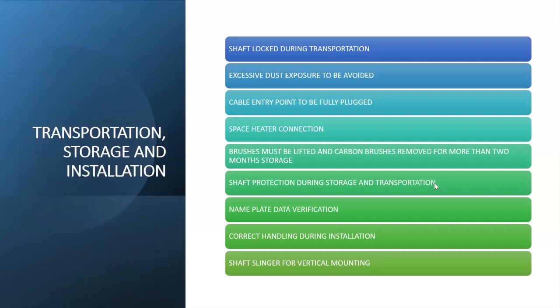is expedient that we do verification of the nameplate data. We do not wait till the day of installation before we are found wanting and we are forced to use the motor for an application that it is not designed for. And when you are forced to use a wrong motor for the right application, chances are that you have a lot of maintenance issues.